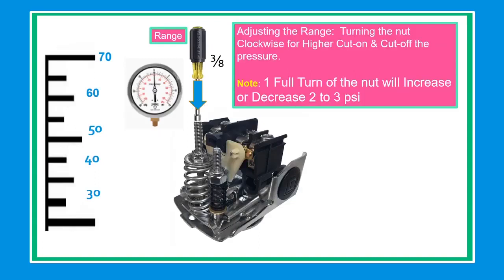By adjusting the center nut, you will lower or raise the range, so you can increase or decrease the pressure by turning clockwise or counterclockwise. Turning the nut clockwise will increase the pressure. Note, one full turn of the nut will increase or decrease the pressure by 2 to 3 psi.